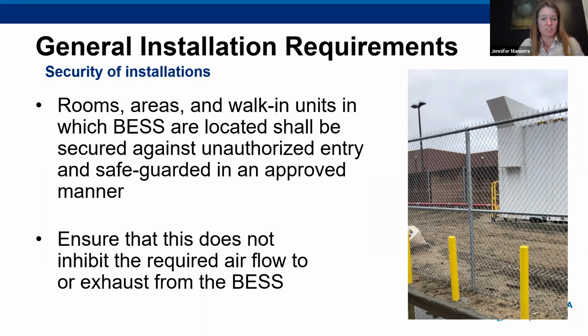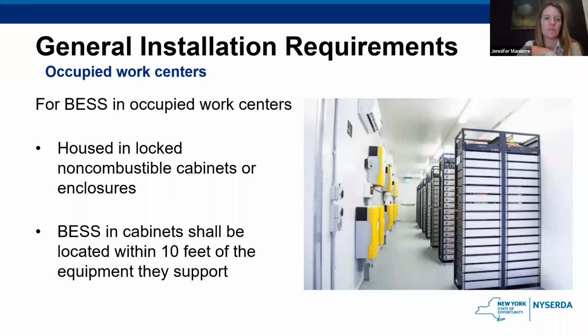Okay, some general installation requirements. There are some security requirements. Any room, area, and walk-in units where there's an energy storage system needs to somehow be secured against unauthorized folks from coming in. In many cases, that security is going to take the form of a fence for an outdoor system, for example. There's a lot of energy stored in there. You don't want someone who doesn't know what they're doing going in and messing around with it. For energy storage that's in some sort of occupied work center, that security would be locked, non-combustible cabinets. And those cabinets, if they're not in a separate room, need to be within 10 feet of the equipment that they're supporting.